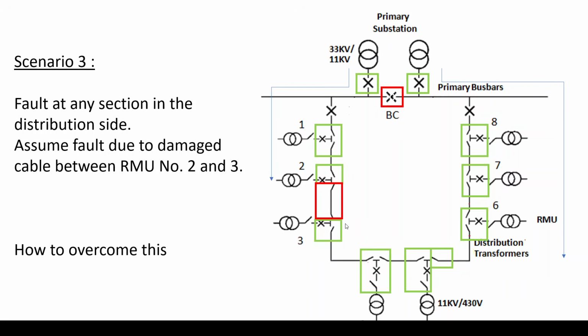But now I have a problem. My cable is faulty here. So what I would do is that this terminal of the RMU would be opened, whether remotely or locally. It would be open from here, and this terminal also will be open in order to isolate this faulty section. So this brings us to the other advantage of the RMU, which we have mentioned earlier: isolating faulty sections of the network for maintenance, and avoiding servicing or replacing this part without any downtime to the remaining part of the distribution network.